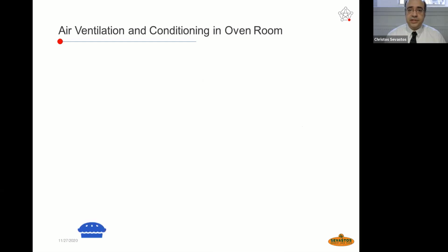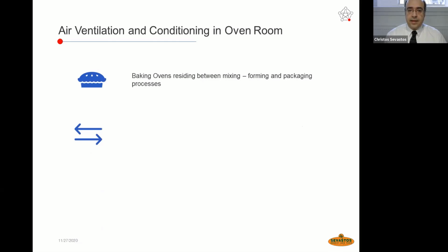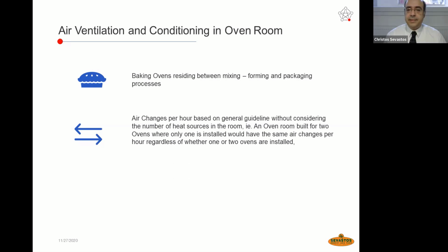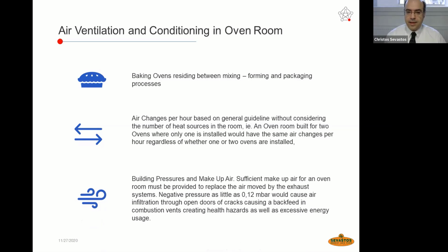Air ventilation and conditioning in the oven room. The baking ovens should be residing between mixing, forming, and packaging processes. The air changes per hour are based on a general guideline without considering the number of heat sources in the room, meaning that if we're going to have an area with one tunnel oven and we're going to designate this area for 2 tunnel ovens, the air changes per hour should be made in terms of 2 tunnel ovens instead of 1, even though we are going to have 1 oven in the area.